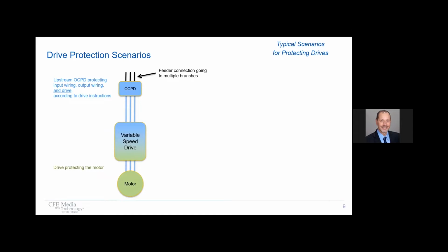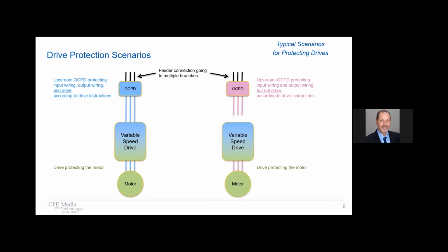Now, it's helpful to look at a few common protection scenarios. Let's first look at a feeder that's serving multiple branches. And off of that feeder, typically there's an overcurrent protective device, being again a breaker or a fuse generally, that's protecting the wiring. In some cases, if that device is chosen properly, it has the ability to also protect the drive. But that's not always the case. So let's look at another case in which the overcurrent protective device is chosen, but according to the drive instructions, it's not the right device to protect the drive. So in that case, an additional or supplemental protection device is required to protect the drive. So now we know that drives nearly always require an external protective device, and sometimes, but not always, can be protected by the same devices that are protecting the branch circuit wiring.